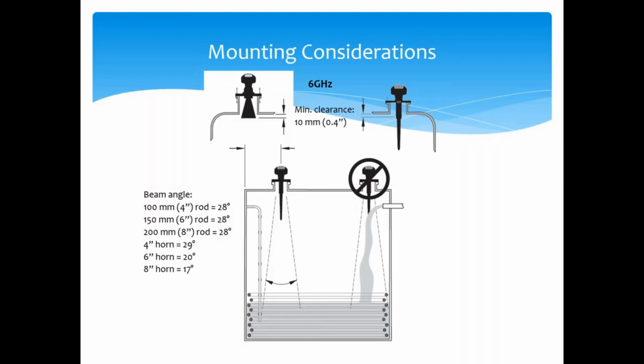The last question we have so far is, would a guided wave radar or an ultrasonic be a better choice over standard radar for liquids with a low dielectric constant? I'm going to assume standard radar refers to non-contact radar. Yes, if you get below a certain dielectric, I'd say anything below 3 we probably want to pay close attention to before recommending a non-contact radar. And anything below 1.5 is really going to be a cutoff point for us. That's where, with things like hydrocarbons or certain oils, vegetable oil or cooking oil, we have very low dielectrics where radar might not be a good option. That radar signal might literally penetrate right through the product in the tank and not see it. So yes, that's where we'd go to an ultrasonic or a guided wave.